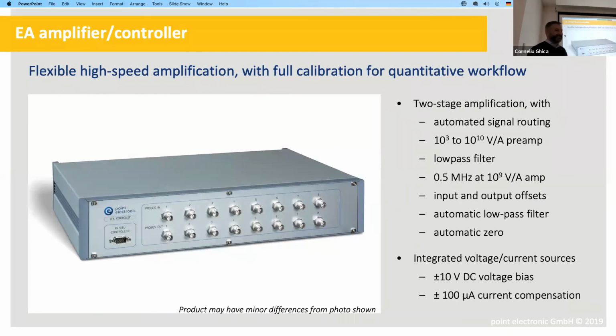Gain is a big deal, so we have to measure very small currents, and we don't really know what kind of thickness of devices you would have and what kind of induced currents you would have. So it has a configurable preamplifier that is very wide range, so it can cope with whatever the experiment would have to. And then because of the speed that we want to go after, we also have low pass filters and the second stage amplification.